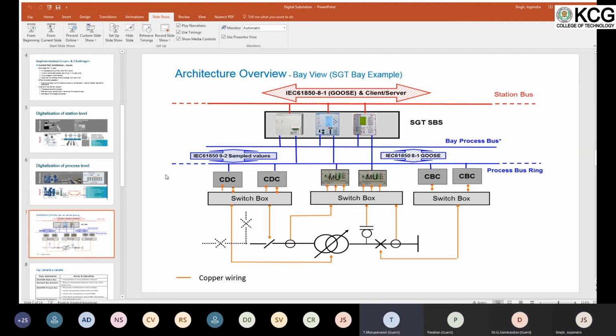The main advantage is that you want to change relays because they have a life of only 15 years. Different assets mature at different times, so you need to change them, and you don't need an outage. Outage is a big cost. I don't know about Indian outage cost, but here in UK, if you want to take an outage of a particular circuit, you need to go to the DNO, and they may not allow it, so it takes a lot of time to agree on the outage.